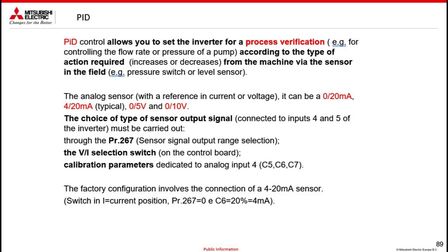Then I will go and define a set point. So the set point is the desired value that I have to keep, and it will correct itself. For example, pump contact, pump and contact. I want to keep 5 bar in the contact. The sensor, the pressure transducer, is a sensor that reads from 0 to 10 volts, which correspond from 0 to 10 bar. So hypothetically, since I want to keep 5 bar, I would like to keep 5 volt, which are 50% of the input signal. I then go and set a set point parameter of 50%.